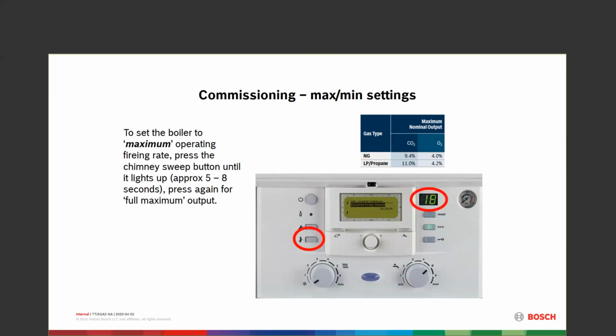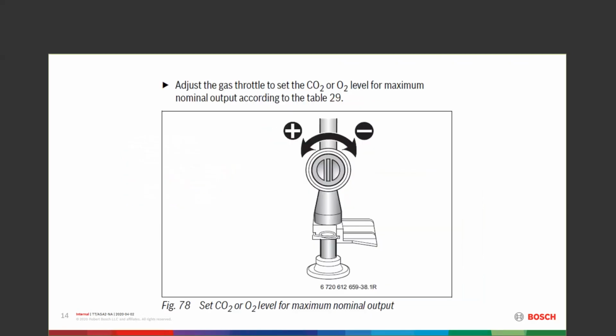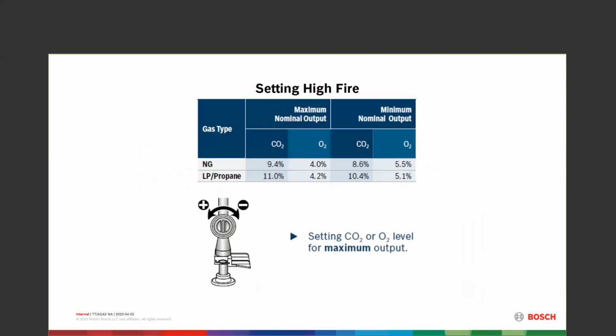You're going to see the display change, and now you should see 4 dashes show up. That's a maximum firing rate that will modulate. The next thing you're going to do is push it again, and you're going to wind up with 6 dashes total. With those 6 dashes, that's maximum firing rate. You're going to adjust using the gas throttle, either up or down, plus for more CO2, minus for less CO2. And the parameters you're looking for are 9.4% CO2, 11% for LP, 8.6 natural in low fire or minimum, and 10.4 for LP low fire minimum.